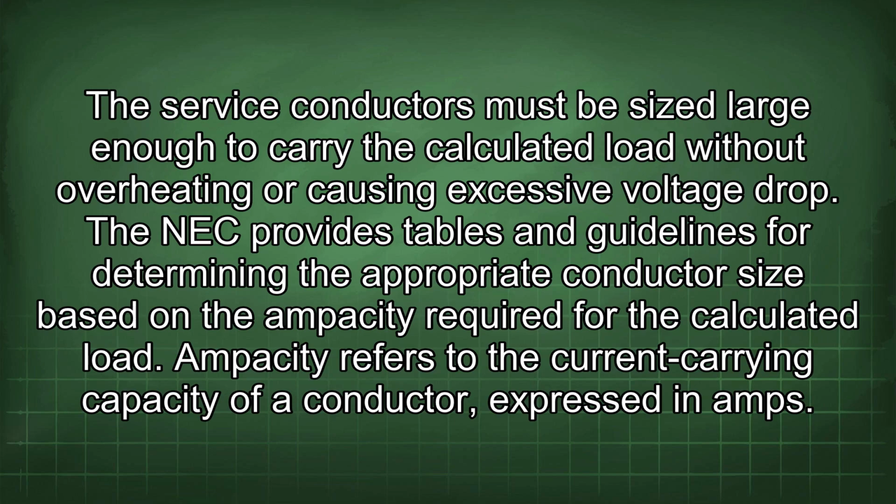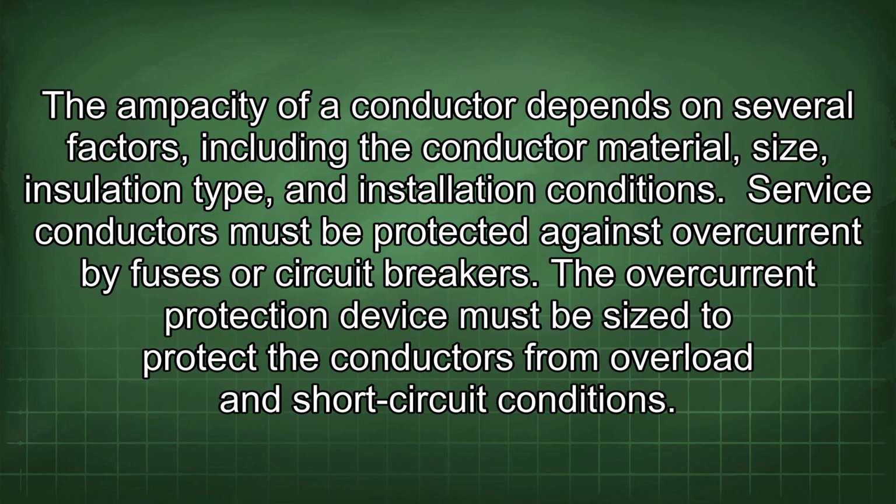The service conductors must be sized large enough to carry the calculated load without overheating or causing excessive voltage drop. The NEC provides tables and guidelines for determining the appropriate conductor size based on the ampacity required for the calculated load. Ampacity refers to the current carrying capacity of a conductor, expressed in amps. The ampacity of a conductor depends on several factors, including the conductor material, size, insulation type, and installation conditions.